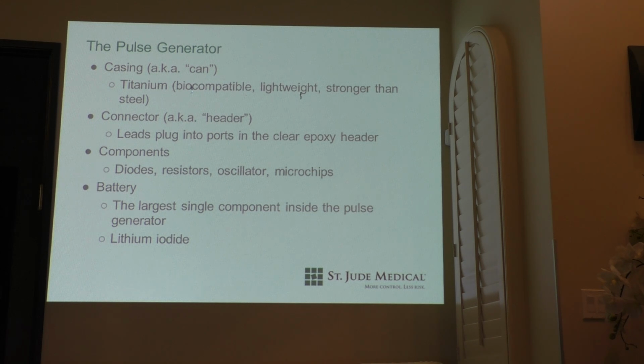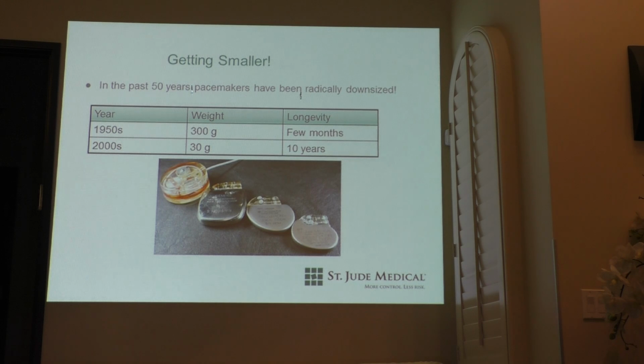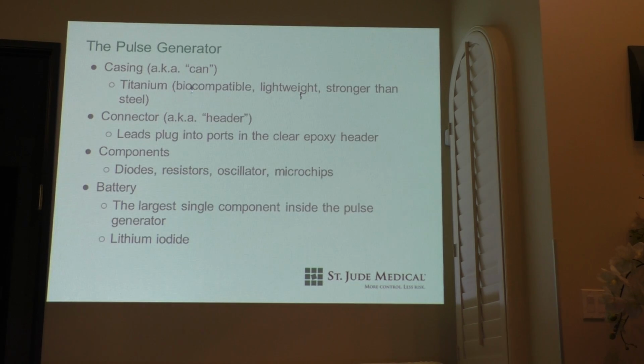So when we put these in, we look for 3 main measurements, and we'll get to that in a second, of a pacemaker, of a pacing system or of a lead. How much voltage does it take to stimulate? How much voltage do we measure for every intrinsic beat? We want that as high as possible. We want the required voltage, otherwise known as the threshold, to be as low as possible, right? Because we run efficiently then. We want to hear really well and not use too much energy. And then the last part is the system resistance, which tells us basically if there's been any changes long term to that circuit. You get a broken circuit, resistance goes up, right? You get a short circuit, resistance goes down, right?